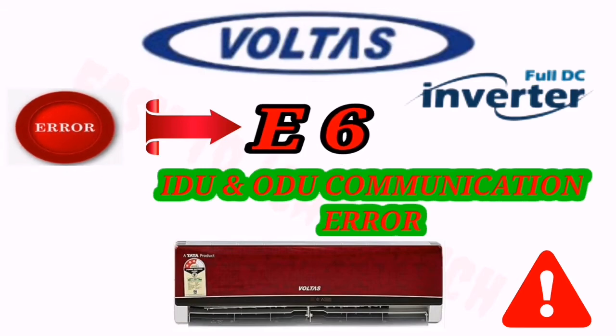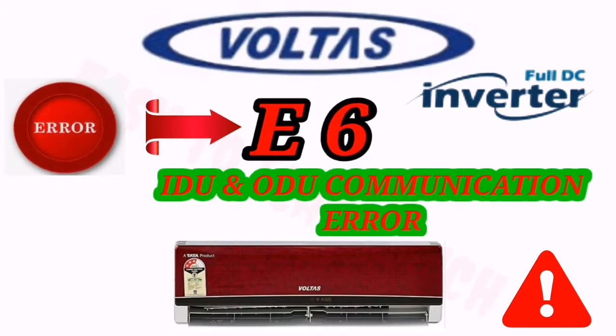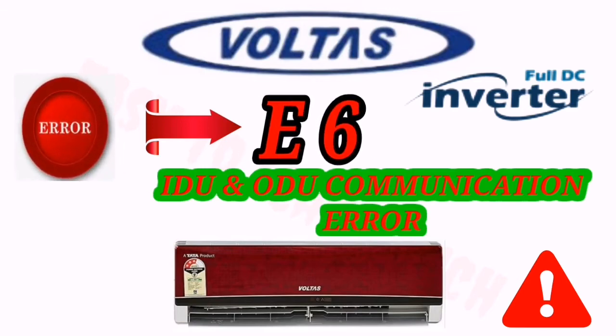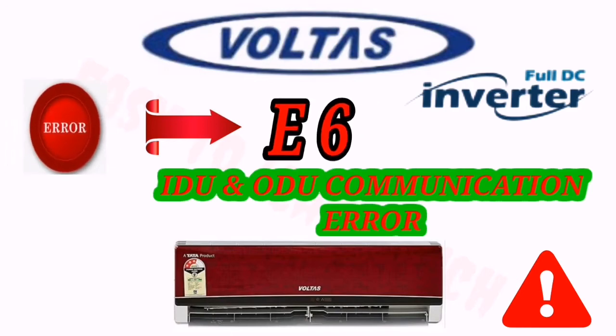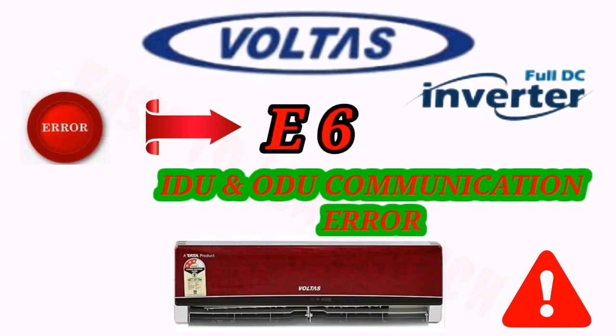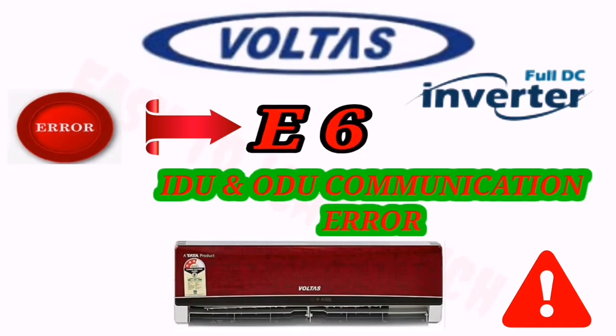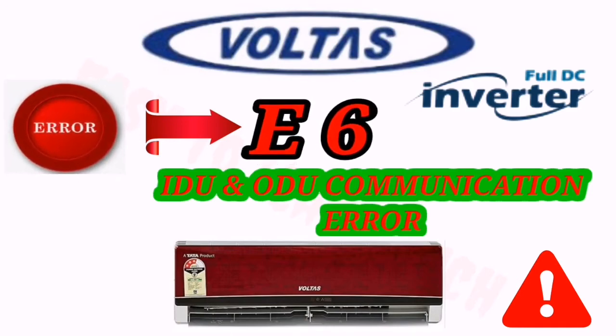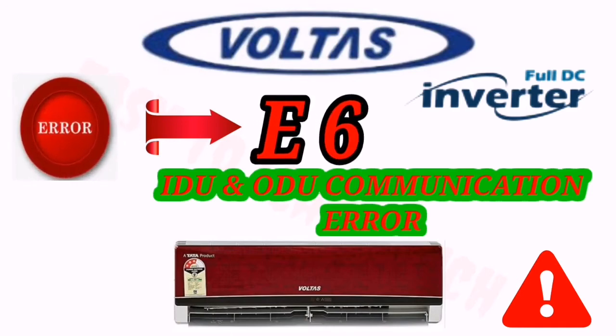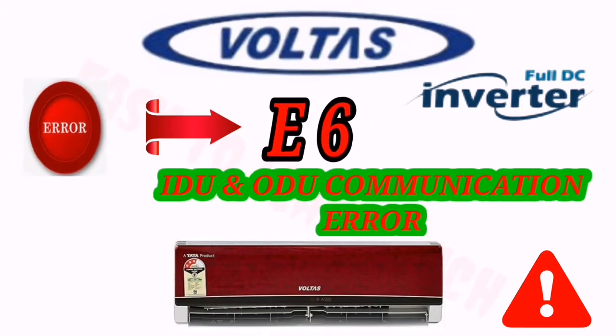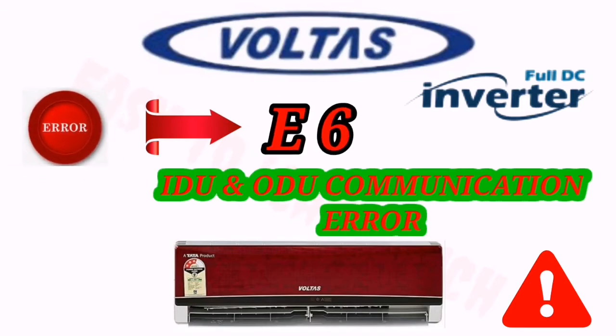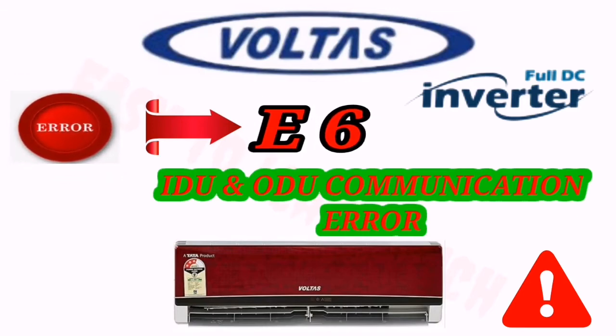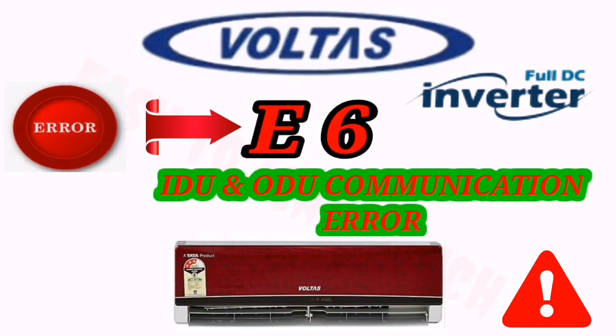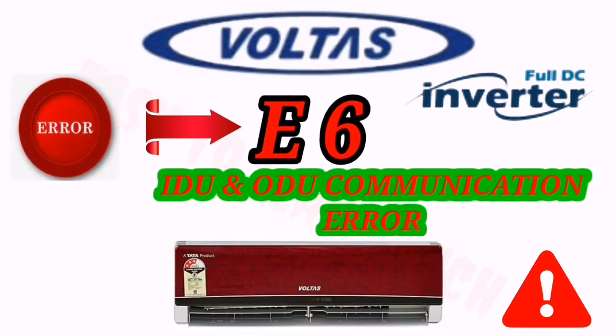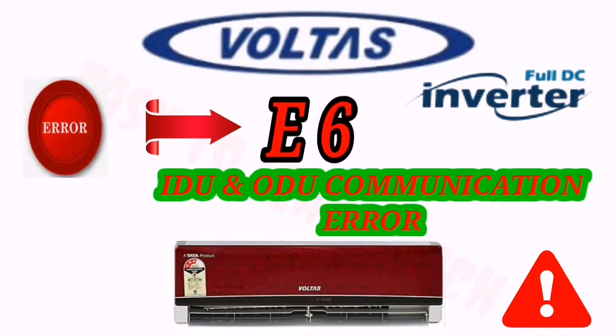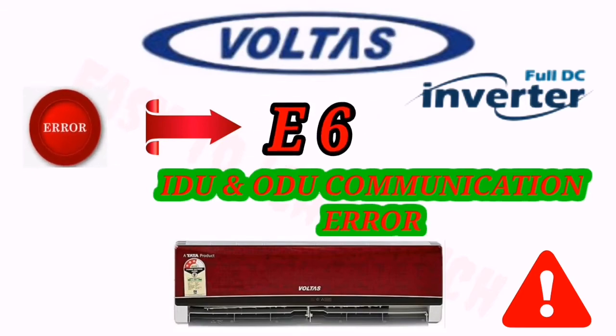And similarly, you have to connect the communication cable to the indoor unit PCB and remove it from the outdoor unit. And again, you have to put the unit on and check if the signal coming from the indoor PCB is between 13 DC volt and 24 DC volt. If our indoor unit is not giving 13 to 24 DC volt, it means our indoor PCB is faulty and needs to be replaced. Then our unit will be in working condition.